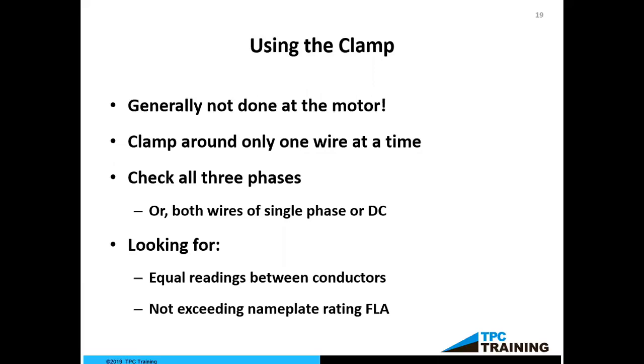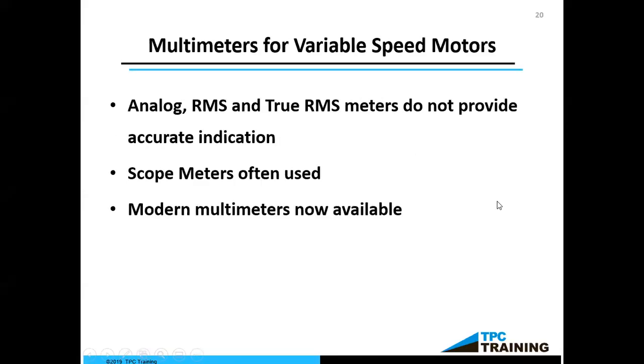That tells me that I haven't overloaded the motor, so the motor's working within its operating range. It tells me that I have no circulating currents going between the windings, which could cause the motor to overheat. And it's a great check. So that's one thing that we can do and look for, and it works out real well.